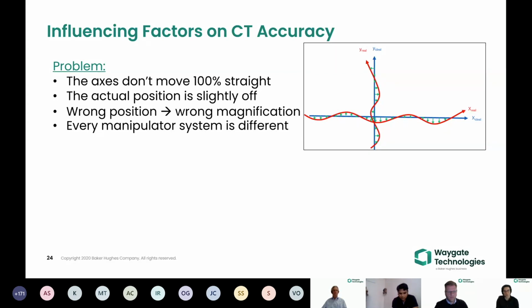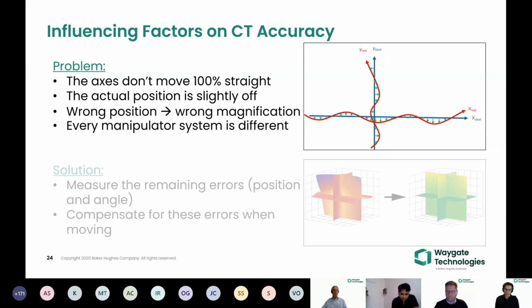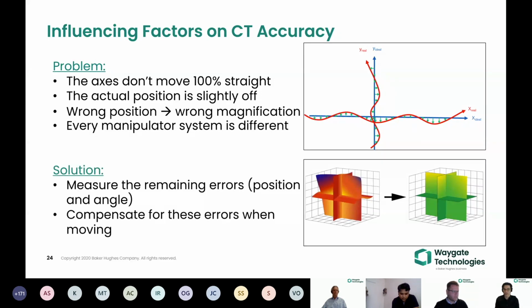So what happens? We are at the wrong position. We have a wrong magnification. We have a wrong voxel size. See, it's always about the voxel size. Again, we have a wrong magnification, wrong voxel size. And of course, this is something that we do not want. So, pretty similar to what we did with the detector, what do we do? Well, we measure it. We have, again, a very sophisticated procedure for measuring the remaining errors of the axes, and we can compensate these errors. So again, we don't have a problem with inaccuracy. We have a problem with inaccuracy that we don't know. If we know it, we can compensate it. So this is now the CNC side of things, so the axes.